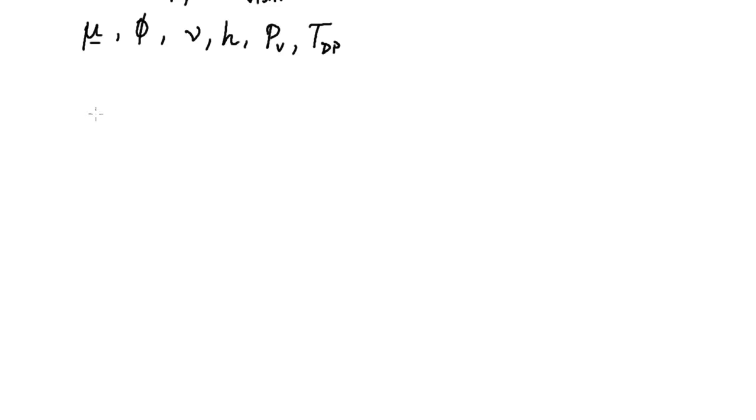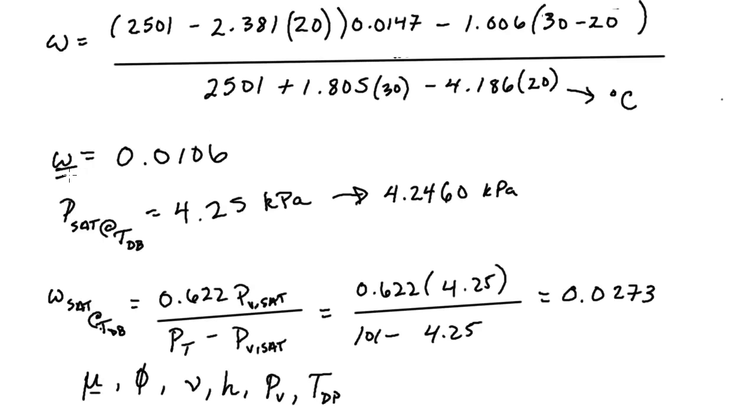And this will be an easy one because we already have the information from what it was defined to be. So mu is defined to be omega divided by the omega at saturation at a given temperature and pressure. And so if we're looking at a temperature of what we have for dry bulb, and we have this total pressure that we've been dealing with, we already calculated out both of these things. So our specific humidity ratio for our sample is 0.0106, and the saturation at the same temperature is 0.0273.